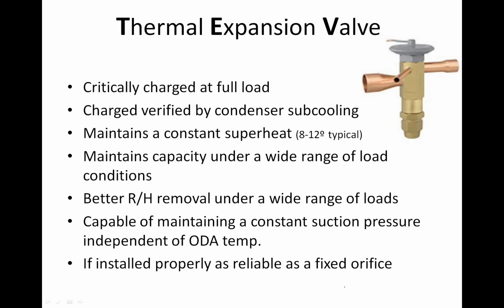In fact, in 20 years, I can say I've probably changed 2 or 3 TXVs, and they're typically due to vibration failure of the bulb capillary tube breaking. Somebody didn't clamp it down. It was an installation error. I don't think I've ever had to replace a TXV because the TXV failed itself. Sorry, sneezed.